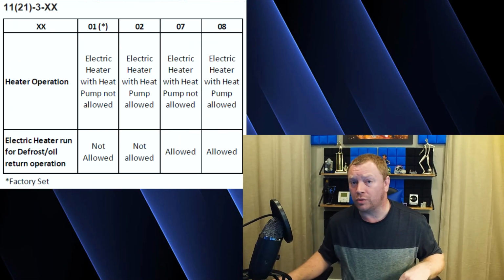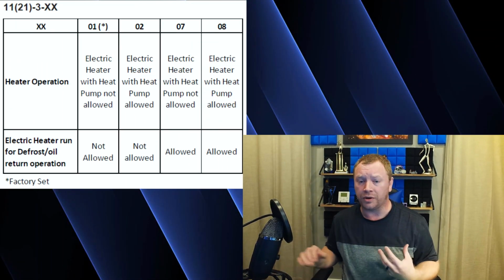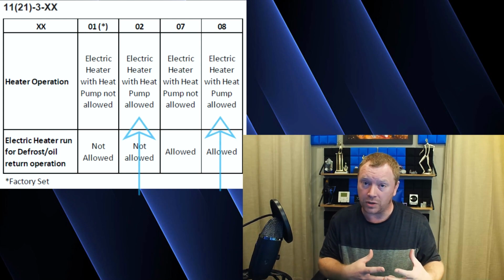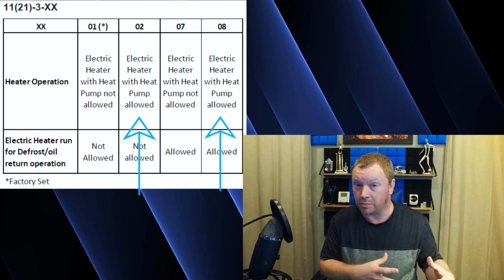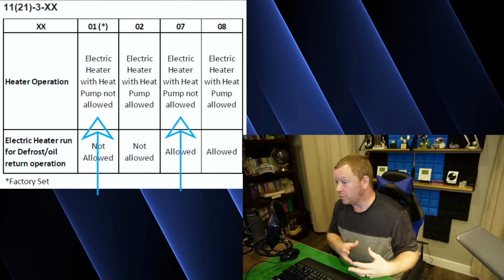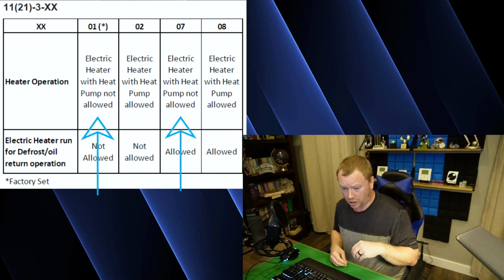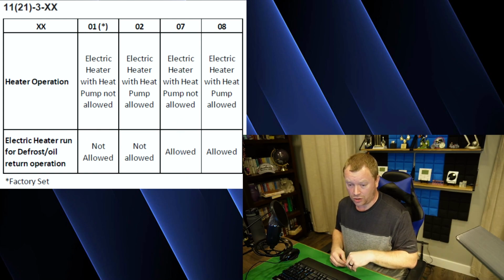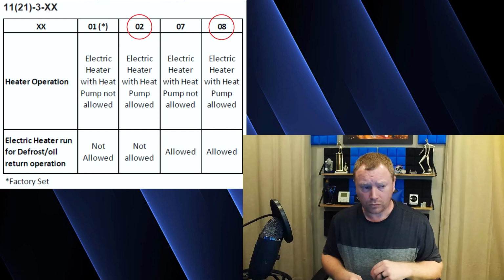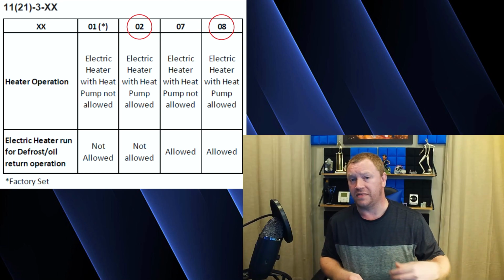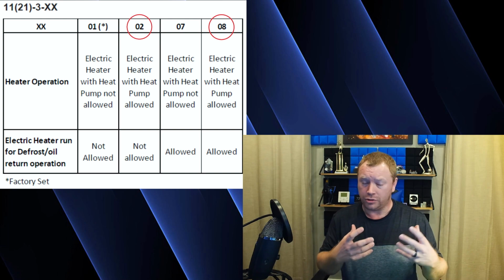But when you have a homeowner that sleeps at 60 degrees and wants to wake up at 70 degrees, you're going to have a problem. What kind of problem are you going to have? Well, let's go back to mode 21, setting 3, where you're going to tell it to either run the strip heat with the heat pump, or not run the strip heat with the heat pump.